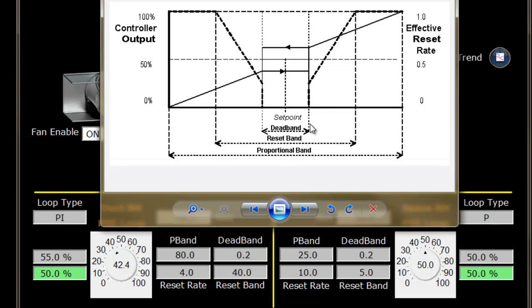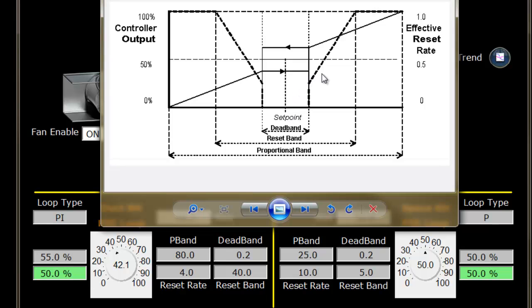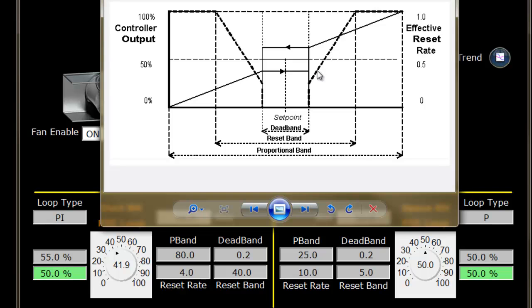The reset rate number we're using is 4. If your input is this far from set point, your effective reset rate would be somewhere around 25% of whatever this is. As you get further from set point, the dashed line moves up to the edge of the reset band.